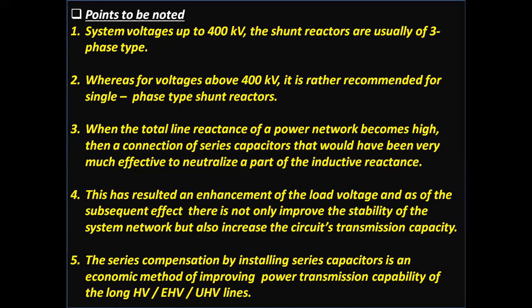When the total line reactance of a power network becomes high, then a connection of series capacitors is very effective to neutralize a part of the inductive reactance. This results in an enhancement of the load voltage, and as a subsequent effect, not only is the stability of the system network improved but the circuit's transmission capacity also increases.